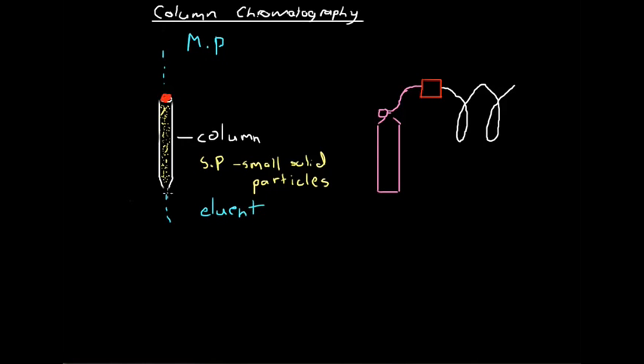In order to form the chromatogram and analyze how long different components are taking to come out, we pass the eluent through a detector. A UV detector is one commonly used — UV light is shone through the eluent stream onto a detector. Depending on what substance is in the eluent at a given time, different amounts of UV light pass through, since different components absorb different amounts. As the makeup of the eluent changes, different amounts of UV light reach the detector, giving varying readings to analyze.